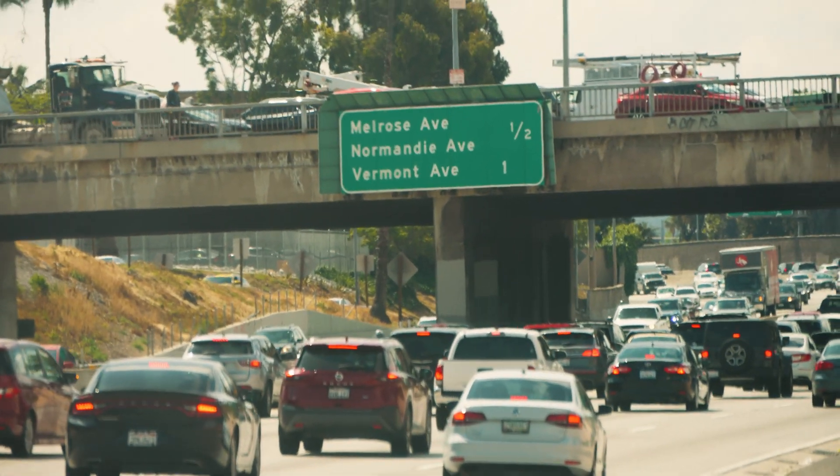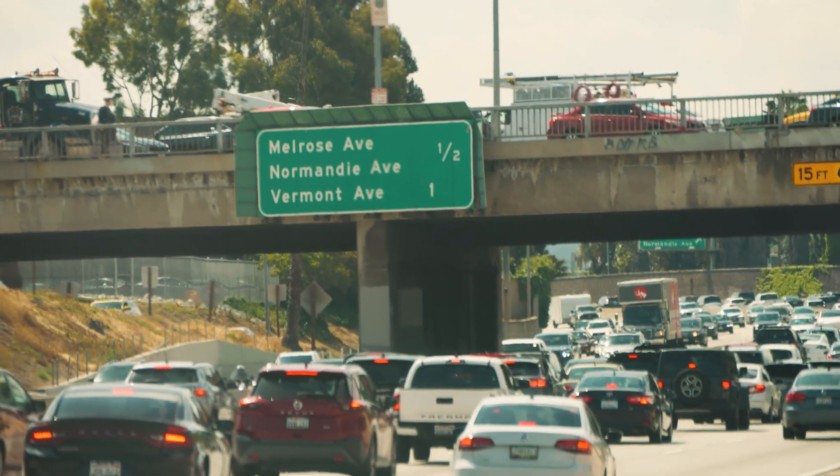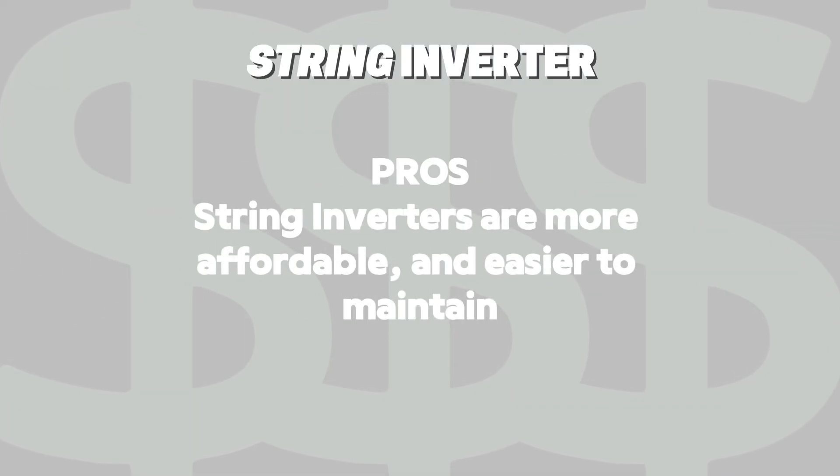Solar panels are wired together in a single lane or string. With a string inverter, if one of those panels underperforms, it will affect the performance of the rest of the panels in that string. Much like rush hour traffic here in LA — when you've got one car that slows down, it slows down all the rest of the cars behind it as well. These types of things can reduce the performance of the system by causing a bottleneck where the rest of the system has to adjust to match the performance of the lowest performing panel. String inverters are lower in cost and can also be easier to maintain because there's only one device that needs to be addressed.